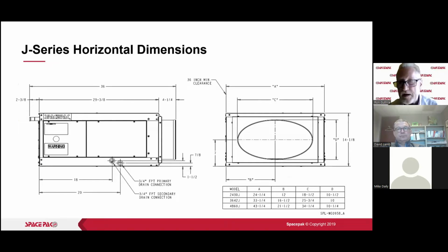We're not going to give you a test on the dimensions here, but what I want to point out is all the way to the right, that 14 1/8 dimension there. That dimension is by design. This unit is made to fit between two joist spaces on center. So I think we got about 14 1/2 inches in between two 16 on center joists. This was originally made to cut out a return hole, really, and the unit will slide through the hole in the ceiling that the return grill will eventually fit into.